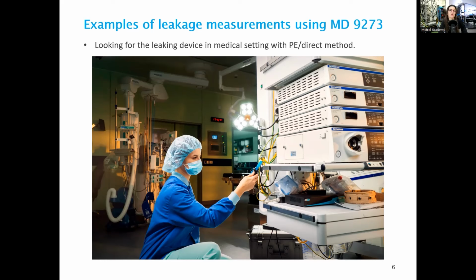However, the MI3110 will only test the safety measures for us, but it cannot point to the source of any problem that it discovers. So this is where our MD9273 will come in handy. Medical devices generally come with external PE wire, separate from the supply wire, which makes it particularly easy to use the direct method of measuring leakage current to locate our problem. Let us look at the video of this application.